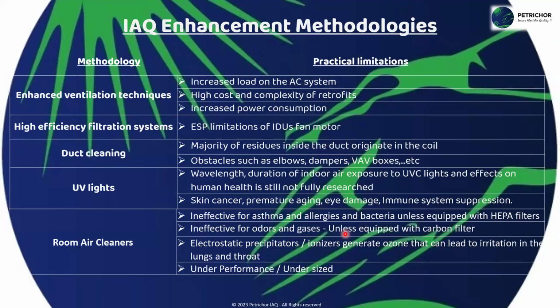Now, we have the high efficiency filtration system, which we also highly recommend for the AHUs. But unfortunately, for existing and even new buildings, when it comes to the FCUs, we find certain limitations with high efficiency filtration, because most fan coils have these small ESP motors. They have a limitation on the amount of pressure drop through the coil plus the ducting, so they really don't have enough ESP to draw the air through high efficiency or HEPA filters.